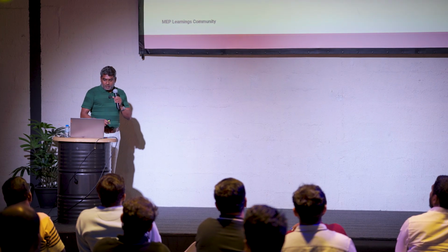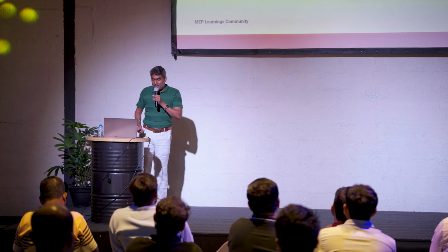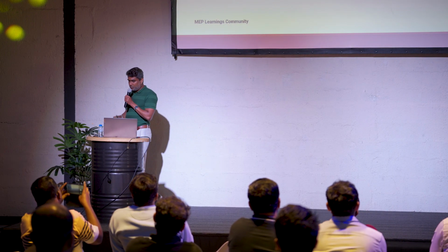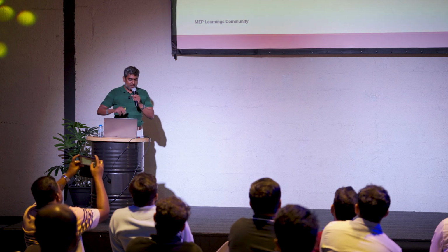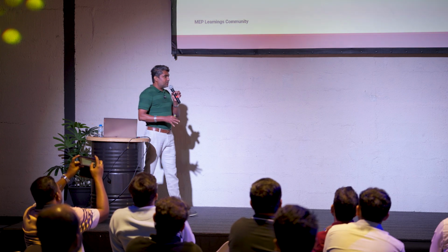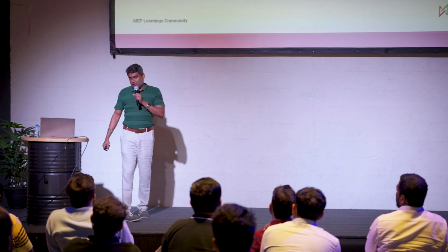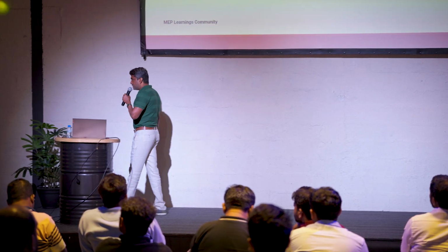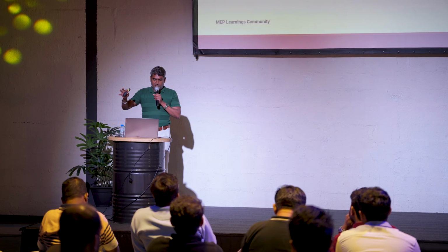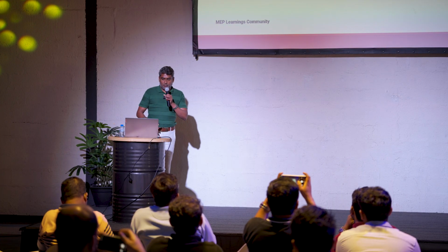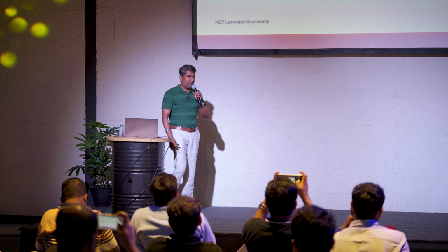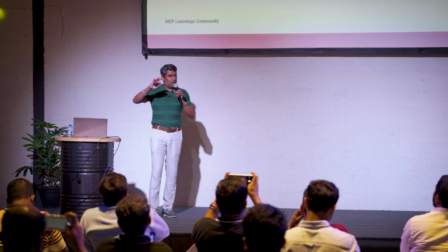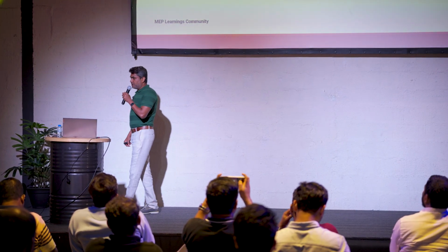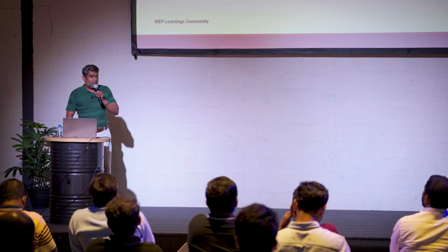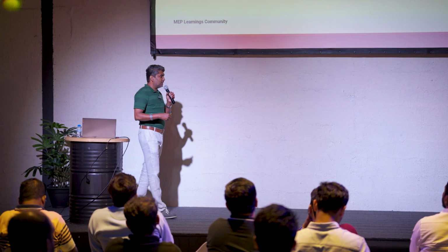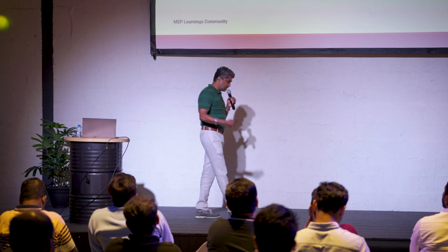The next item is the voice evacuation system. I'm not going to go deep into that, but the most important thing when you design a voice evacuation system is at least 63 dB—correct me if I'm wrong. 63 dB should be the minimum, or 15 dB above ambient noise, is the design criteria. When you are placing speakers, this should be your design criteria, and make sure speech intelligibility is covered in your specification.